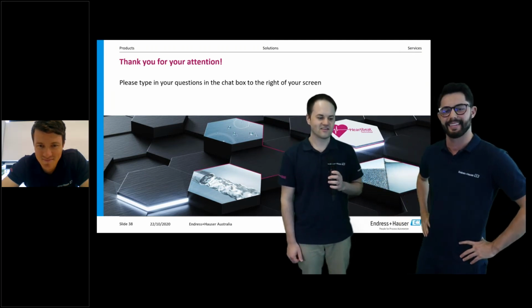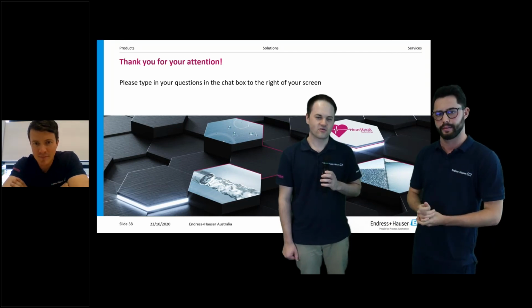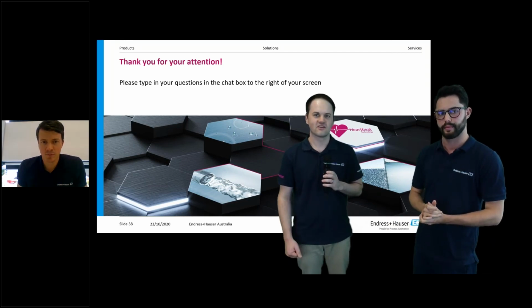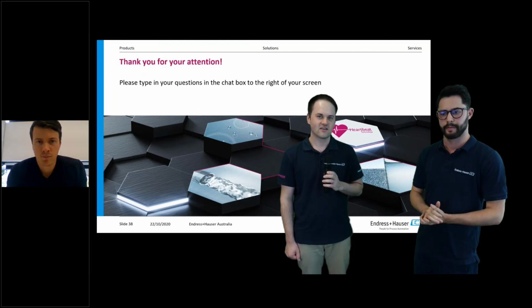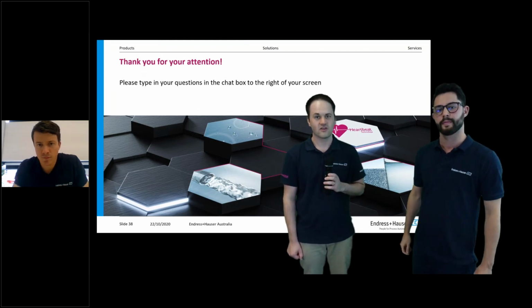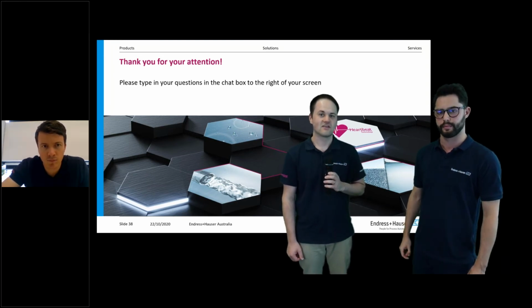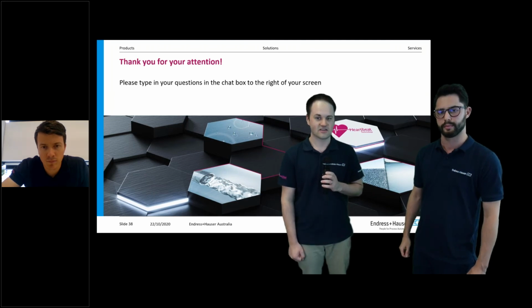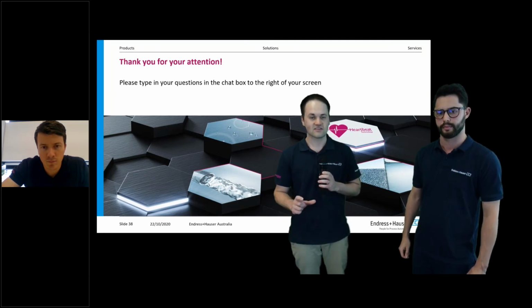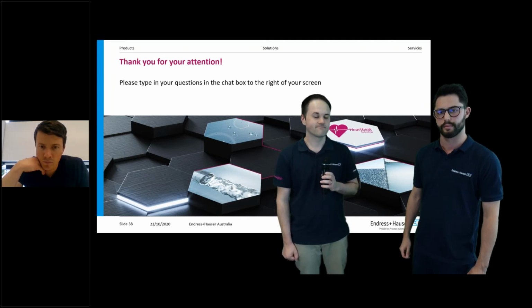In the serial number, you can enter that into the common equipment record, which you can get information around whether the device has heartbeat. Of course, you can also have a look at the nameplate. It will have an extended order code, and you can type that in on our website, and it will give the configuration of that device. You can see if one of the options is heartbeat technology, and if it does have heartbeat technology, then you can use it to verify the device.